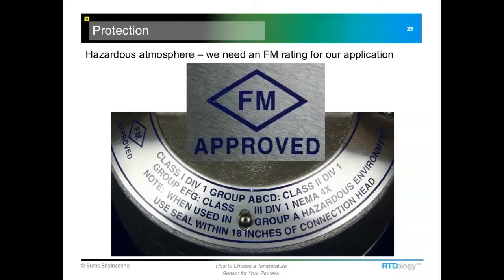This head, and I guess we can't see it on here, but it has the connection head part number on the other part of the label, and it says that it's enclosure only, and this is the rating on it. The assembly with this head on it will have another tag on it that has the actual rating for the complete assembly, because you can use a head that has a higher rating on a lower rated temperature assembly. I hope that makes sense. It can get very confusing, and I'm just looking at Factory Mutual. There are others. There's ATEX, there's IEC, there's the Canadian Standards, CSA, and they'll have a little different rating scheme, it seems, and we can certainly help out if anybody has specific questions about that kind of installation.